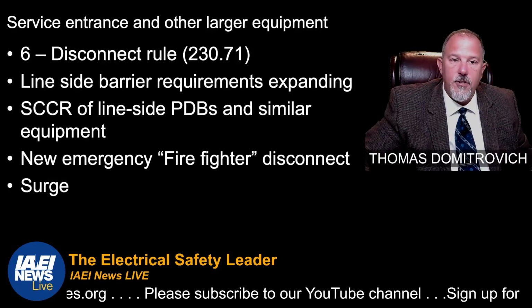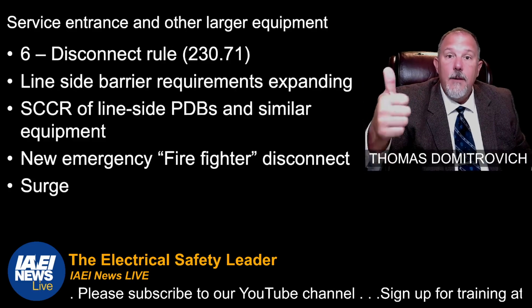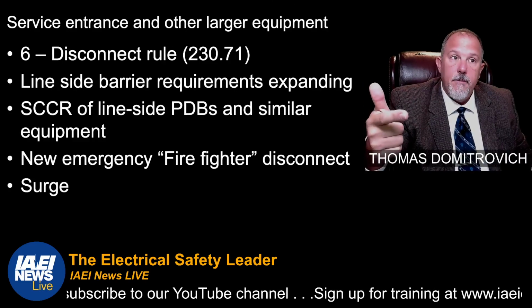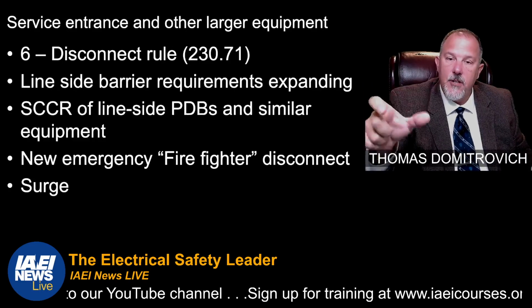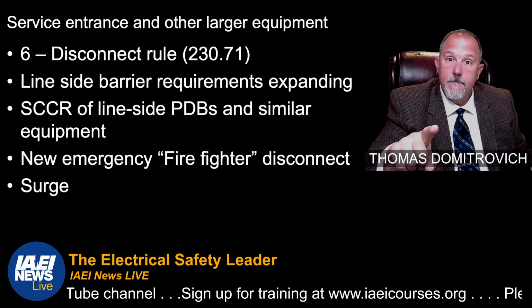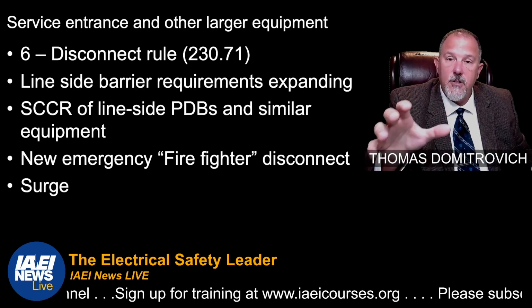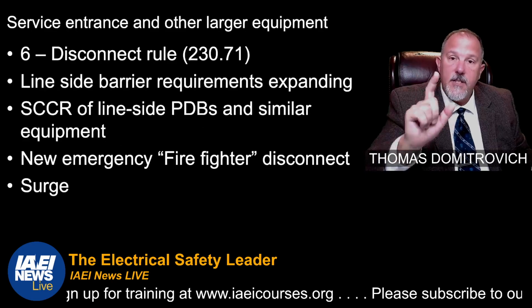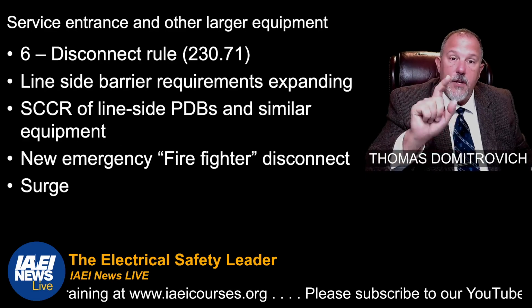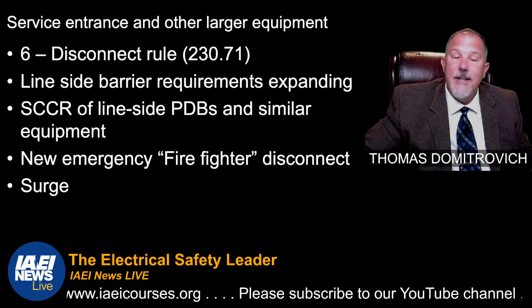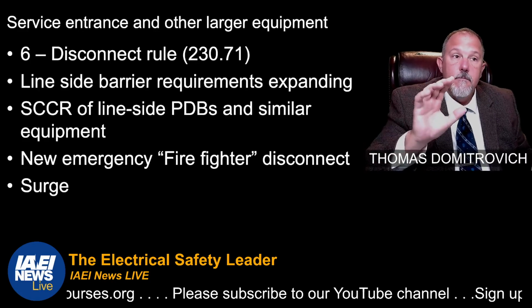Service entrance and other larger equipment. You have the 6 disconnect rule. You're never going to see a service entrance panel board without a main. It's service entrance rated. You're not going to see it without a main overcurrent device because of the changes in 230.71. Keep that in mind.